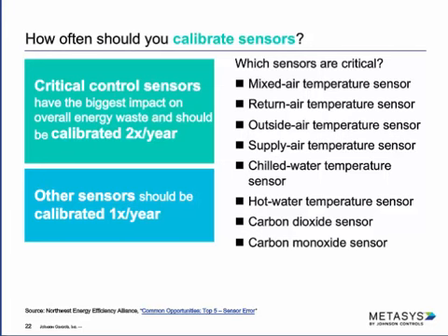And this reliance on manual calibration is reduced. But most buildings are older and don't have this newer technology, so you've really got to be thinking about this twice-a-year schedule. Other sensors, like zone sensors, are less critical to energy savings and to the operation of the equipment itself, so they can really be calibrated once a year.